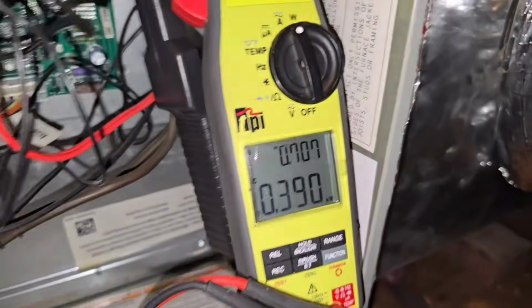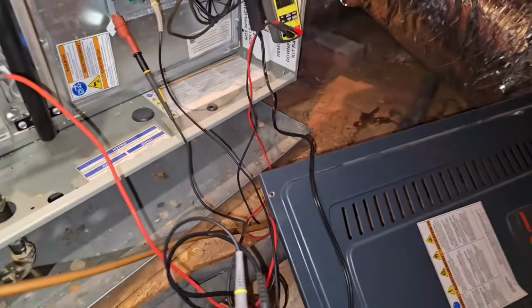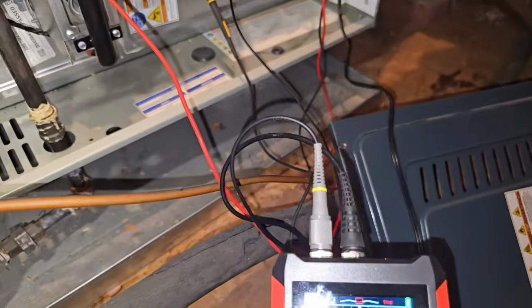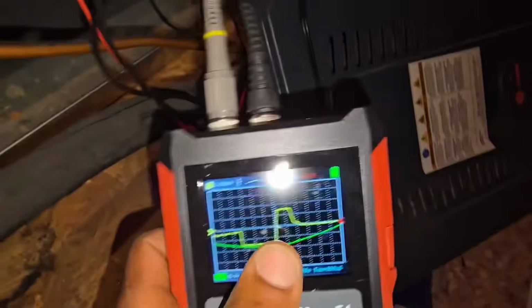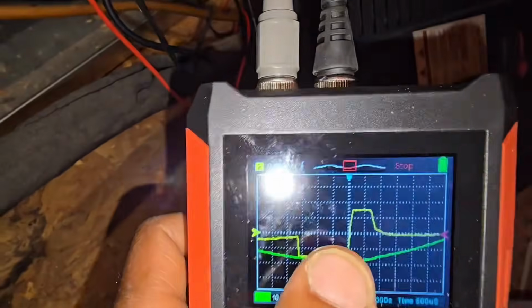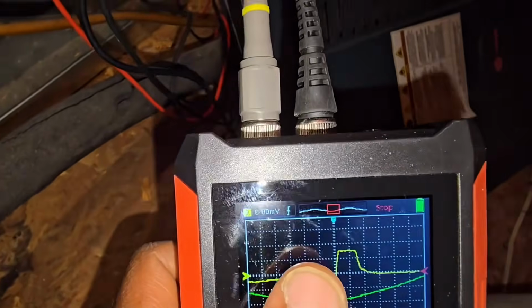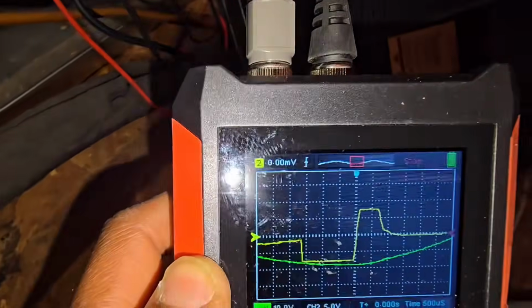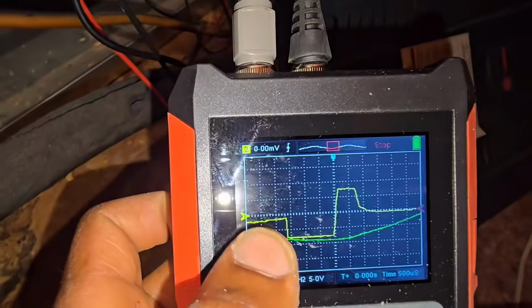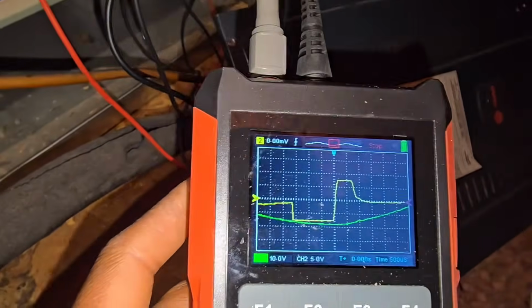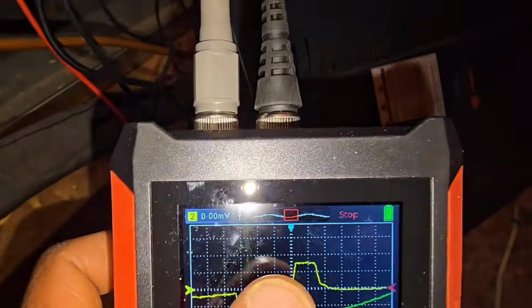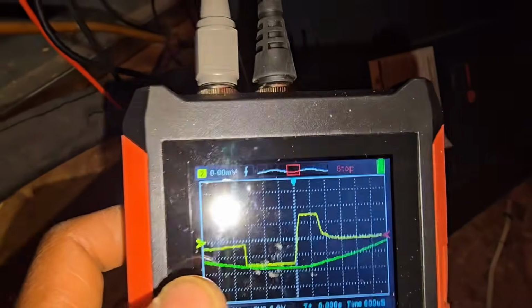So 0.7, because we got a 0.7 power factor. If you multiply that times 0.7, you get 6. So it's showing you this is your power factor. It's showing 70% is going to be in phase with our voltage, and then the remaining 30% is going to be out of phase of our voltage.